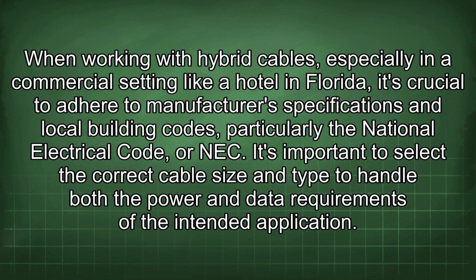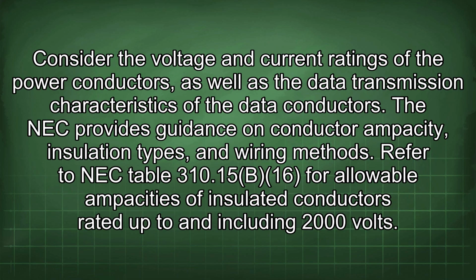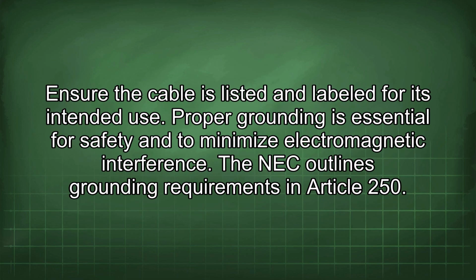It's important to select the correct cable size and type to handle both the power and data requirements of the intended application. Consider the voltage and current ratings of the power conductors, as well as the data transmission characteristics of the data conductors. The NEC provides guidance on conductor ampacity, insulation types, and wiring methods. Refer to NEC Table 310.15(B)(16) for allowable ampacities of insulated conductors rated up to and including 2000 volts. Ensure the cable is listed and labeled for its intended use.